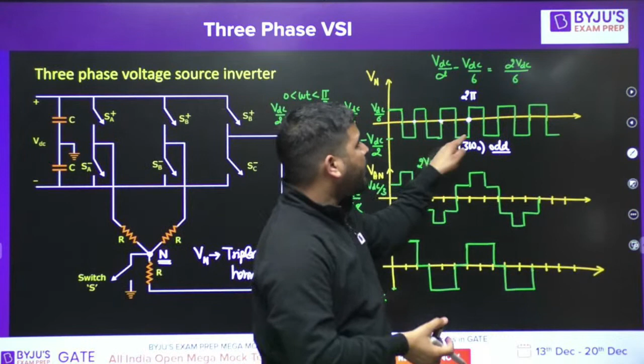Odd multiple of 3 omega naught means this neutral voltage contains only the triplen harmonics. And this other voltage contains triplen harmonics as well as other odd multiples of omega naught, like fundamental, 5th, 7th, including triplen harmonics. So at VAO, you have triplen as well as other odd harmonics, while at the neutral point you have only triplen harmonics. So if you take the difference, the phase voltage will not have triplen harmonics because they will be cancelled, since both VAO and Vn contain the triplen harmonic.